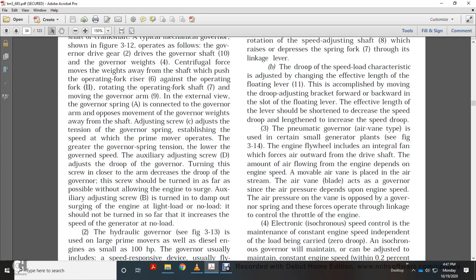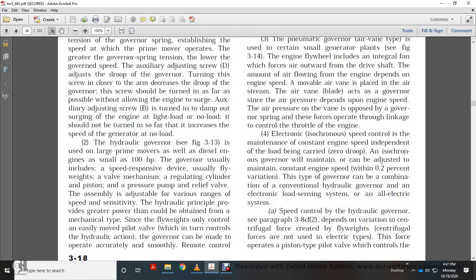The pneumatic air vane governor is usually used with small generator sets. The engine flywheel includes an integral fan that forces air outward; air flow depends on engine speed. A movable air vane placed in the airstream acts as the governor since air pressure depends on engine speed. Air pressure on the vane is opposed by the governor spring, and the resulting force operates through linkage to control the engine throttle. The electronic isochronous speed control maintains engine speed independent of load — zero droop.